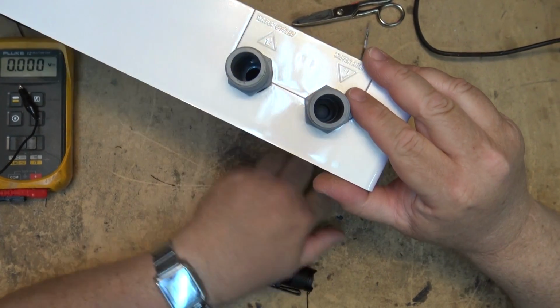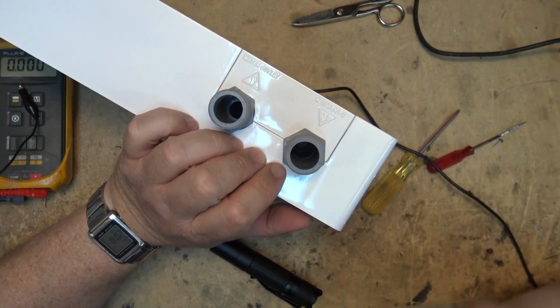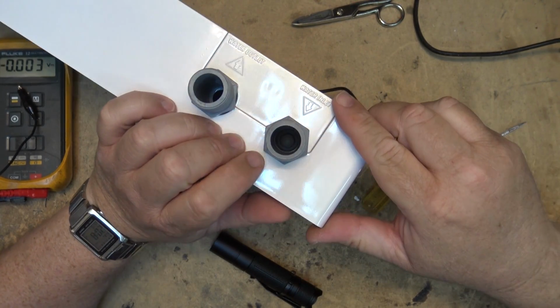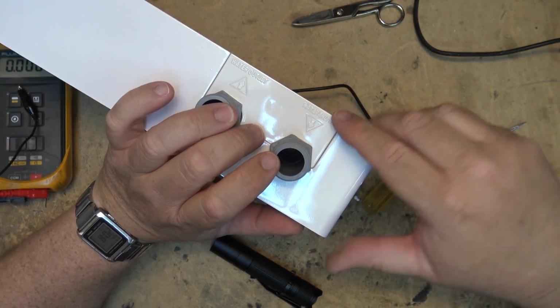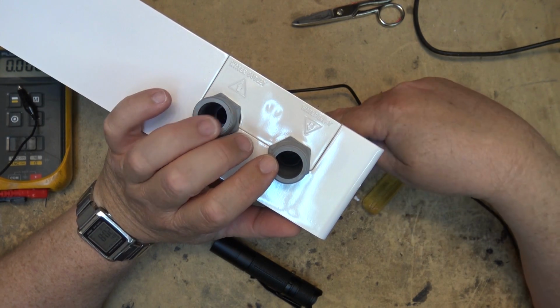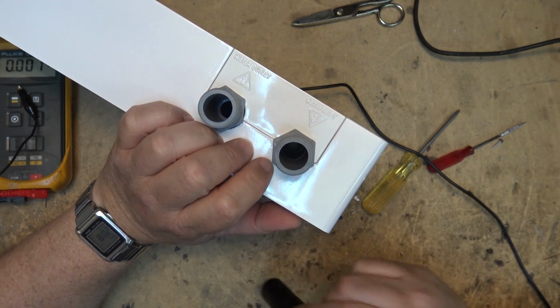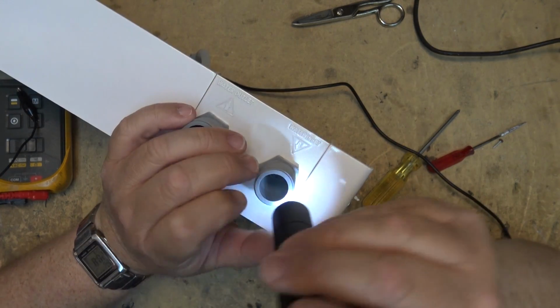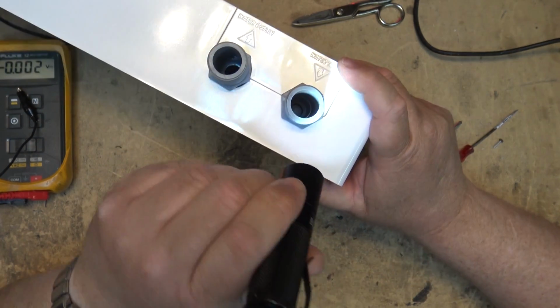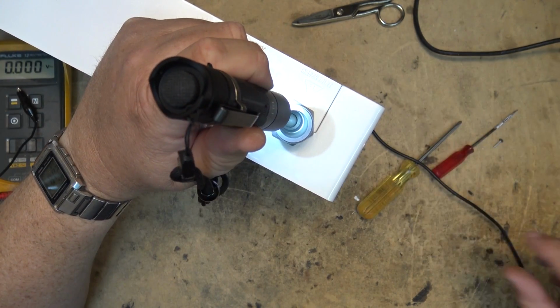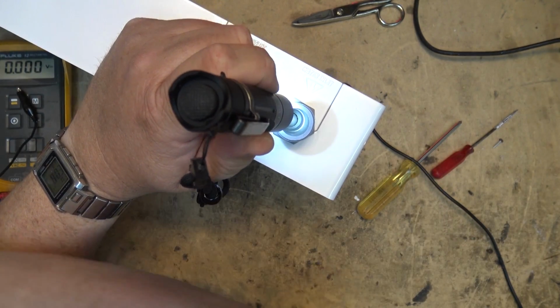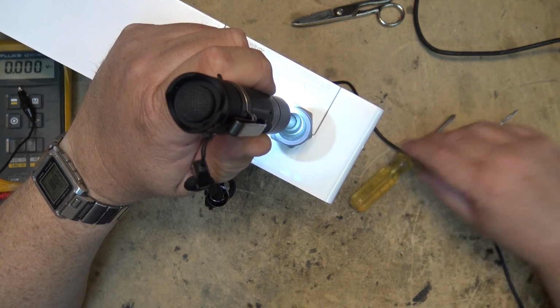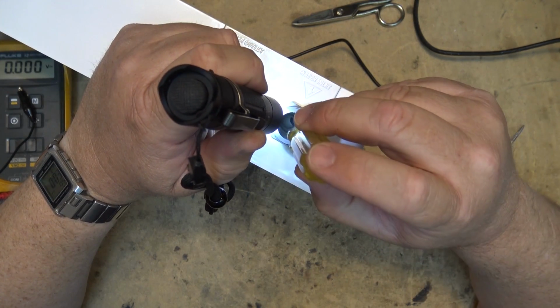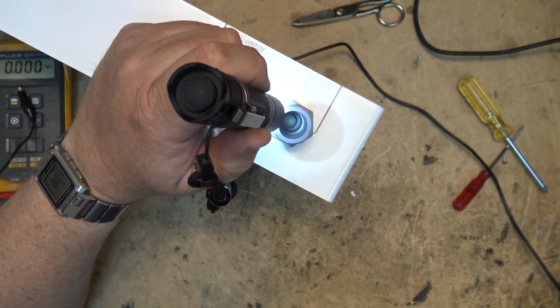So what the flow sensor is, if you look down here, all the flow sensor is, it's just a ball. Then when the water flows through here, it presses this ball up. If I shine my flashlight in here, you guys will be able to see it probably a little easier, but there's a plastic ball in there. So if I use a screwdriver or something to depress that, this should turn on. I guess that one's not quite long enough. Find something that's big enough here to trigger that.